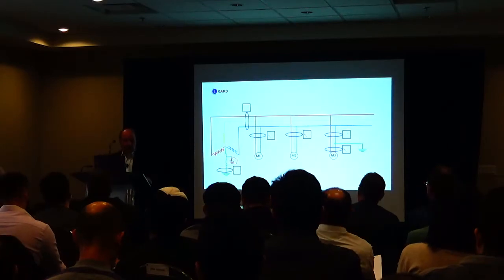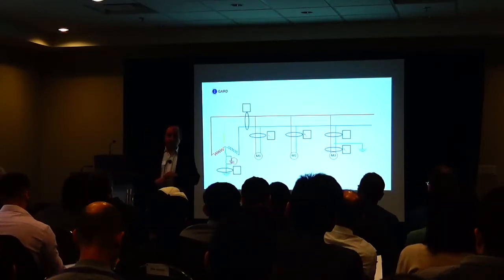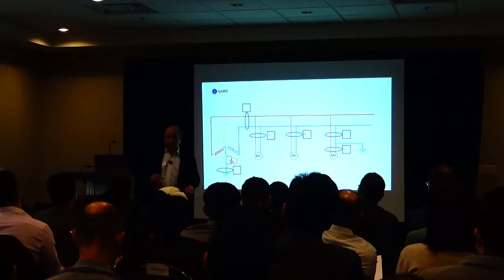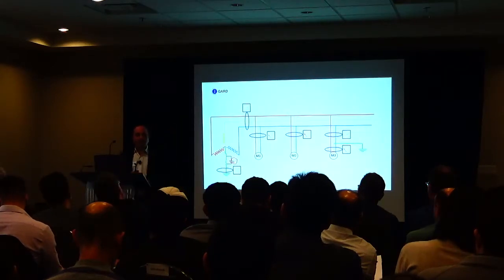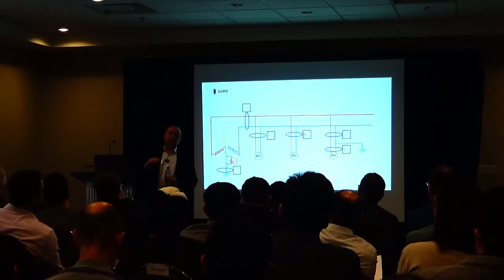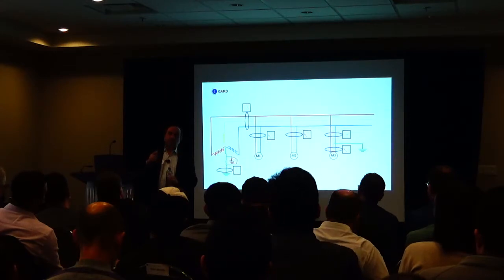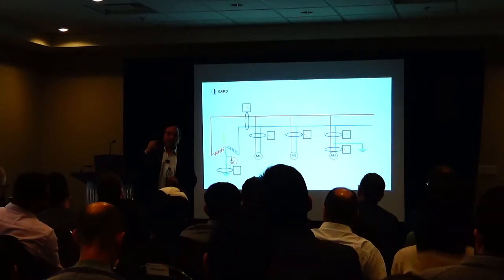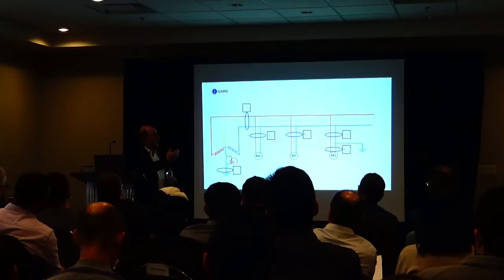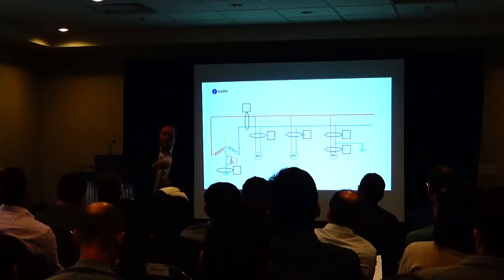And let's assume you don't have a distributed neutral, but you have 347 volt lighting. So now you put in a step-down transformer from 600 to 347. Now your electricians are changing ballast with a 100 kVA transformer instead of your 2 MVA transformer out front. Much less incident energy, it's safer for them.